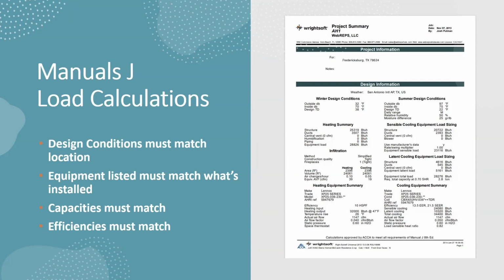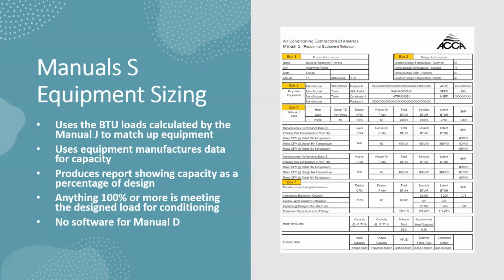And then, after that, the manual S shows the equipment manufacturer's data output in BTUs, which needs to meet or come close to equaling what the BTUs were on the manual J. So again, looking at equipment capacity as a percent of design - this is showing 105%, meaning the equipment matches the load on this house, not oversized, not undersized, but as close a match as possible. There's only so much you can do with the data from the manufacturer; you can't just ask for a specific BTU output.